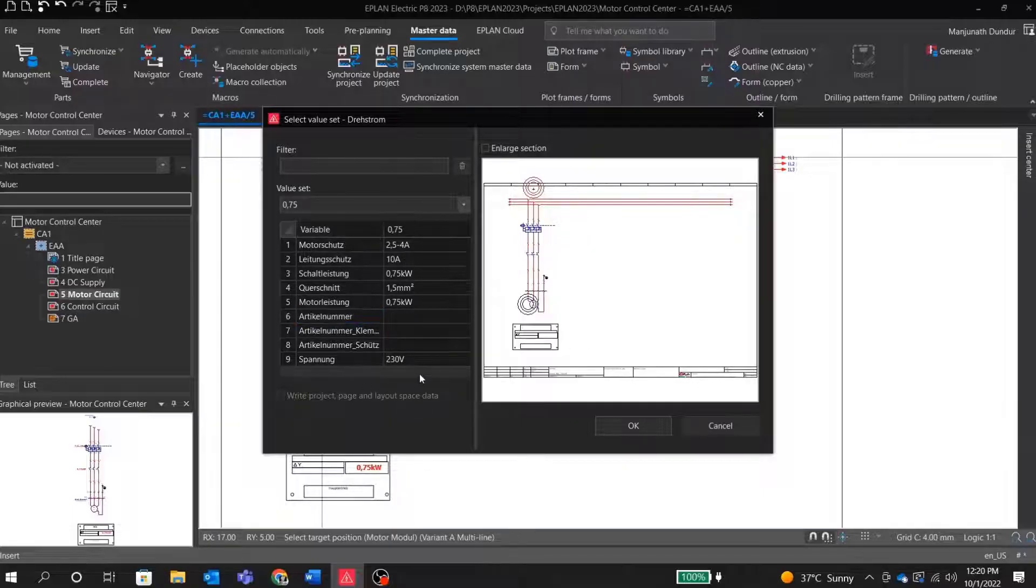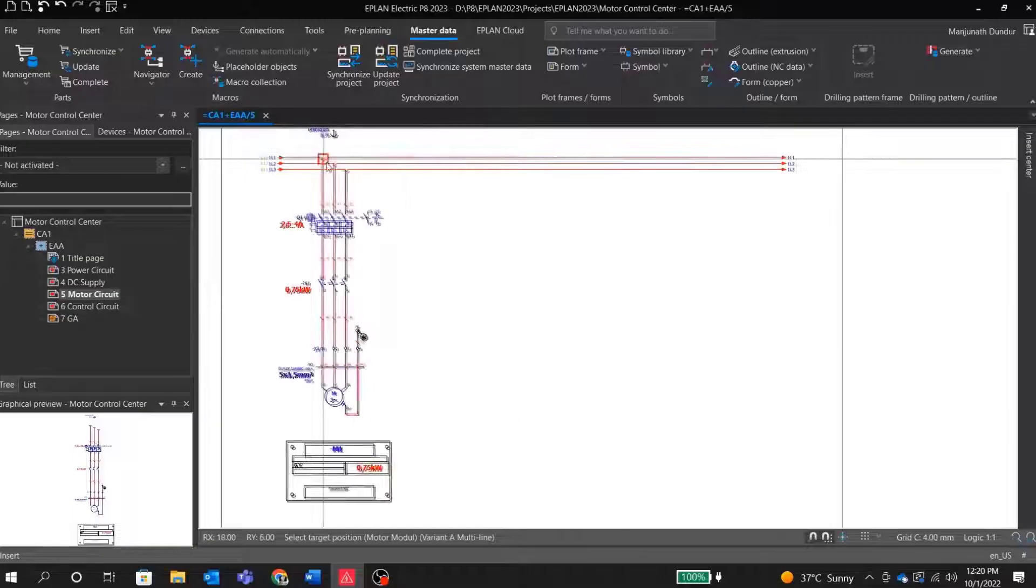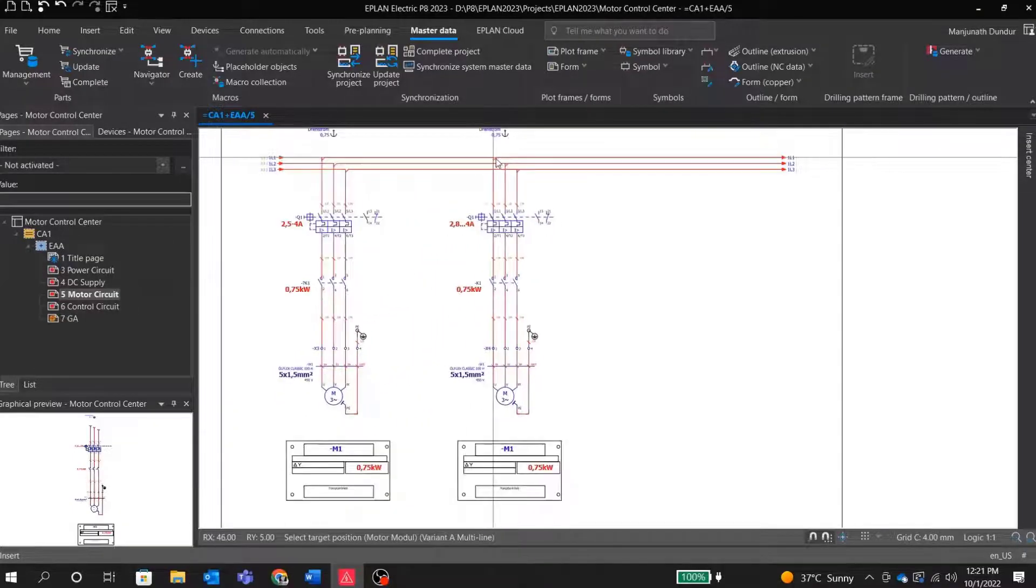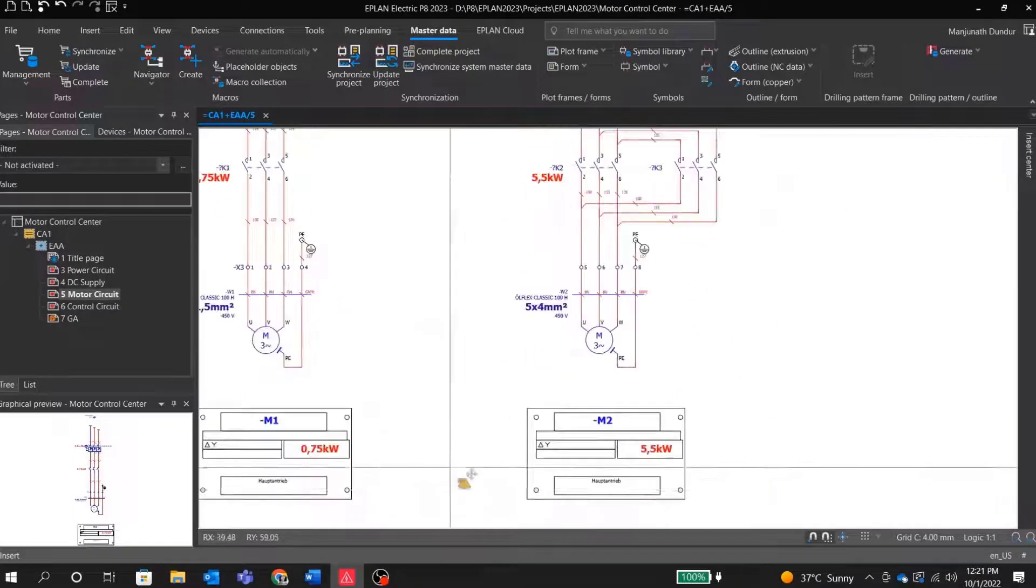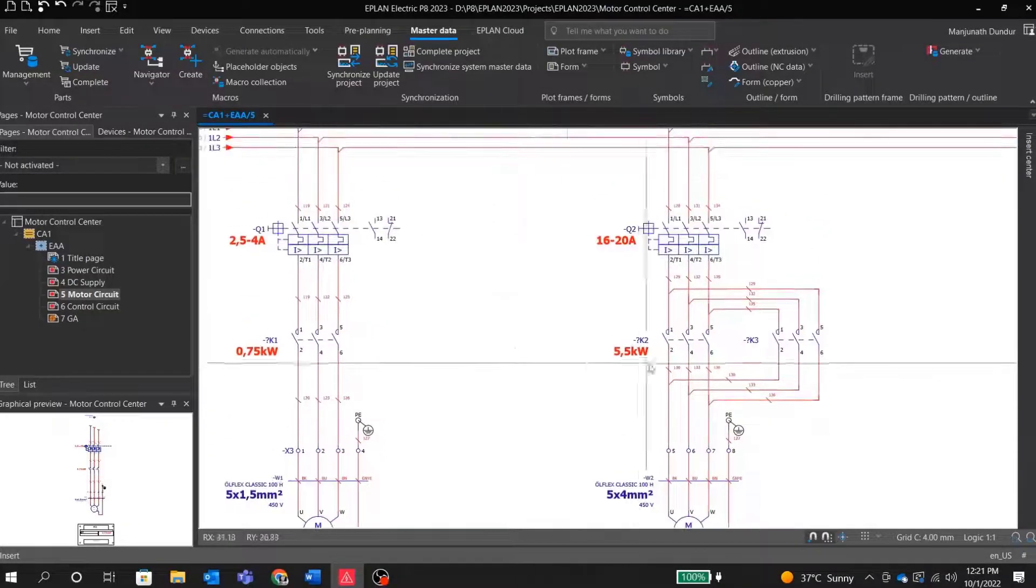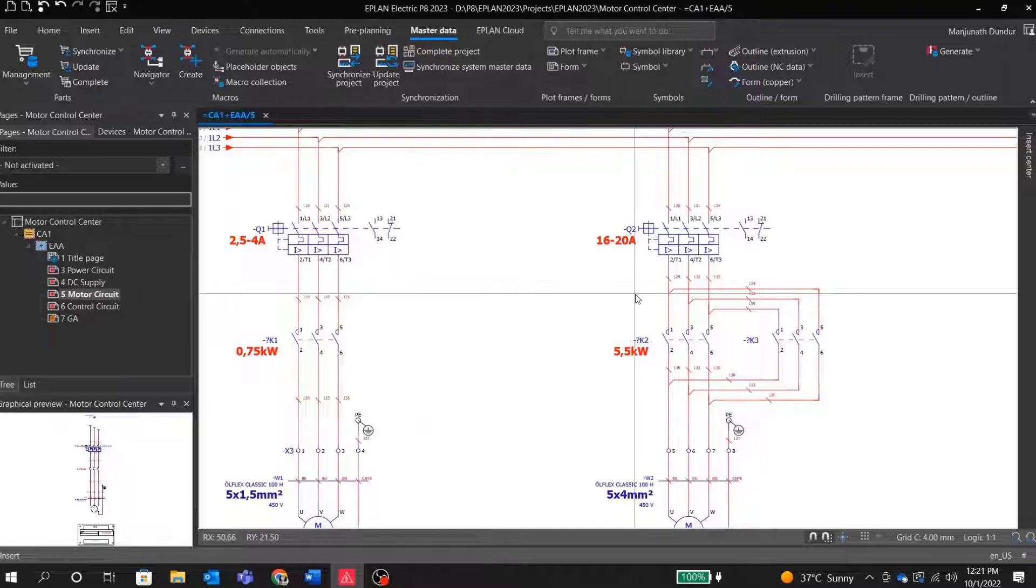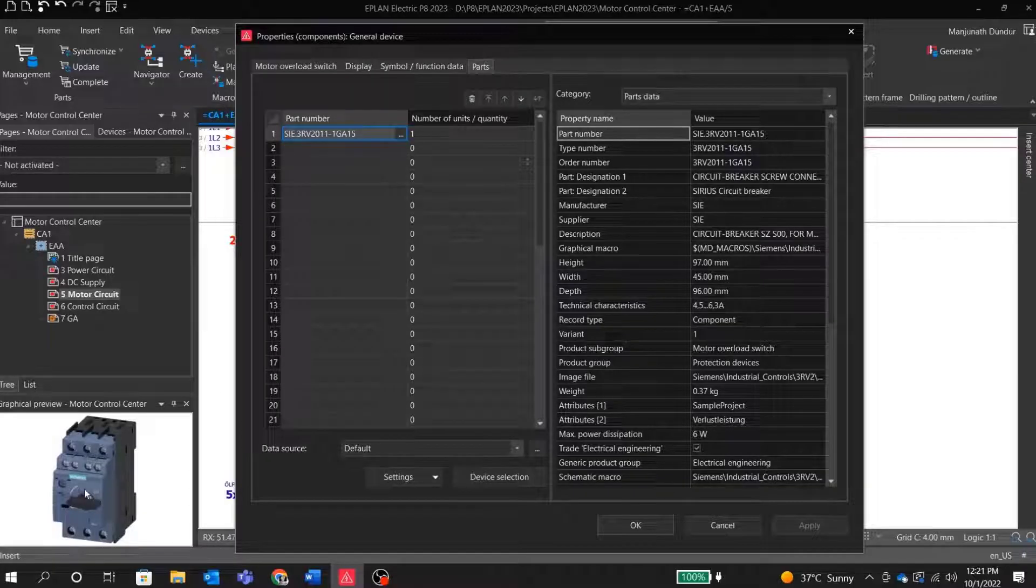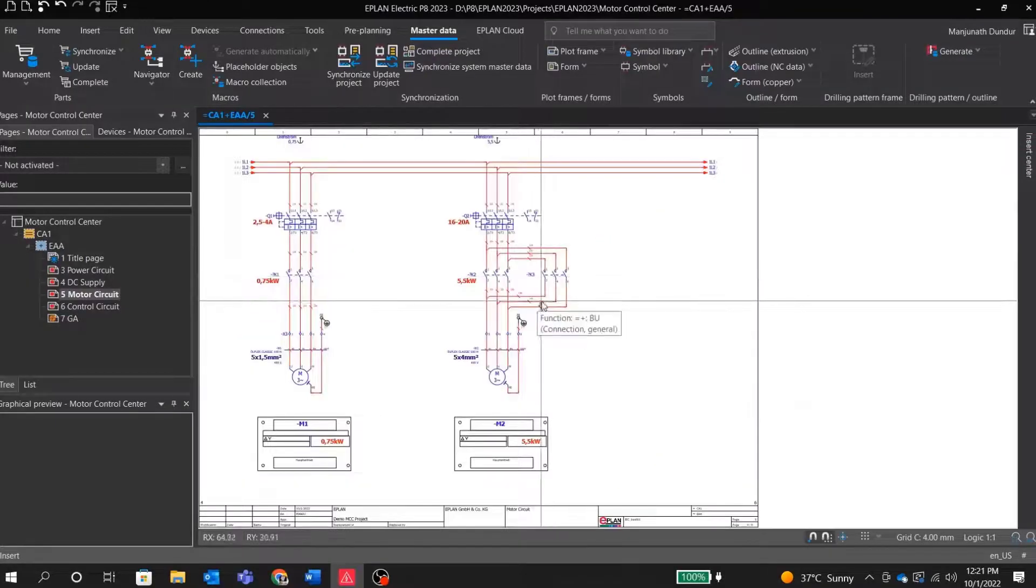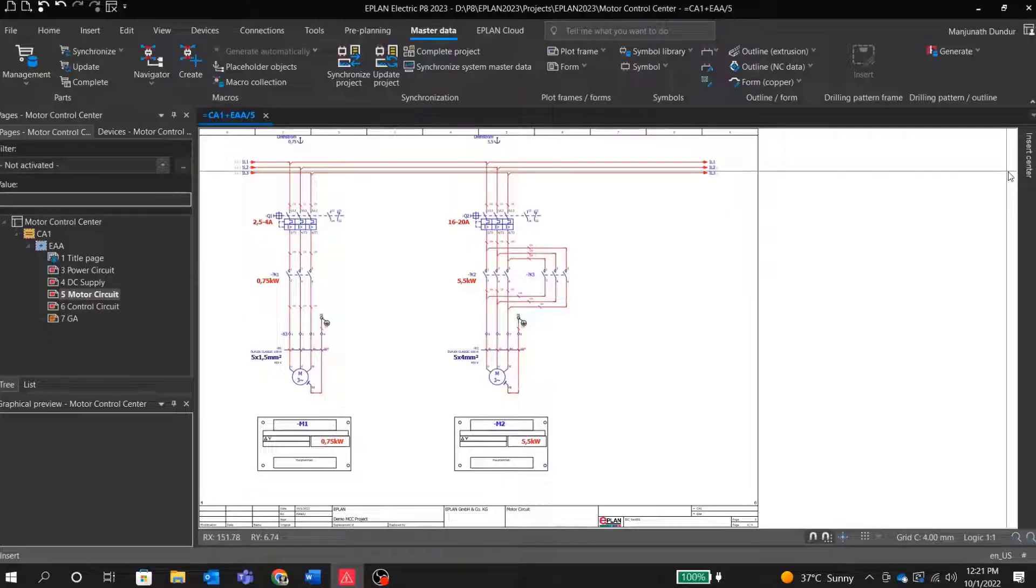Next, as you remember from our video on reading electrical drawings, I want another starter for forward and reverse. This time, let's select 5.5 kW rating for a 5.5 kilowatt motor. As soon as we place that, you can see motor ratings are updated. The cable sizes are updated. Contact details, breaker details, all of these details are automatically updated, including the part numbers and accessories. Based on that, your reports and bill of material will also be automatically updated. You can, of course, create your own macro or block. It is a completely open platform.